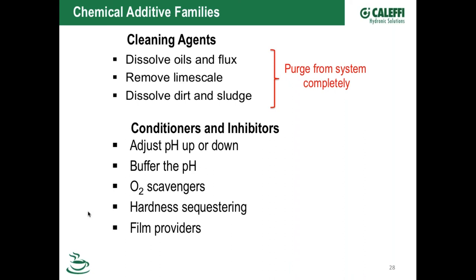The oxygen scavengers are chemical. I know they're using different polymers, different chemicals these days. It used to be like a sulfite that we put in there. So it basically consumes or uses up any leftover oxygen that you didn't get purged out when you heated up your boiler and got all your dissolved air out through your air purger. If there's any O2 left in there, we're going to scavenge that out.